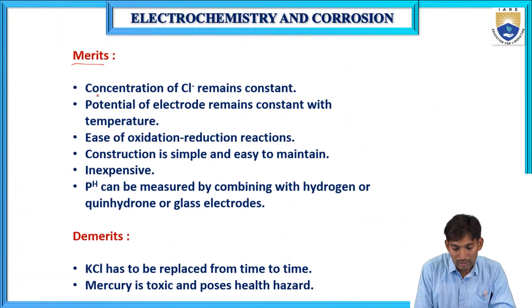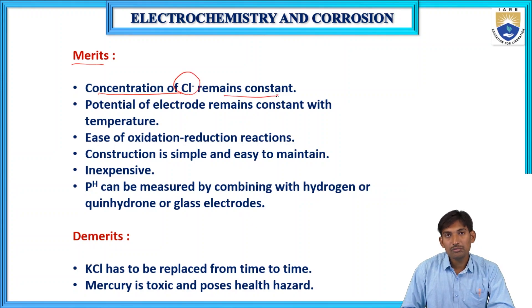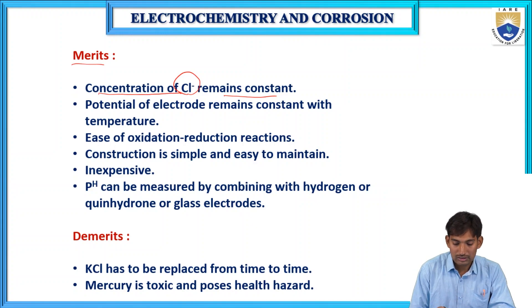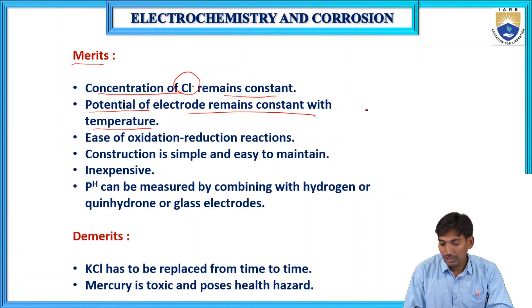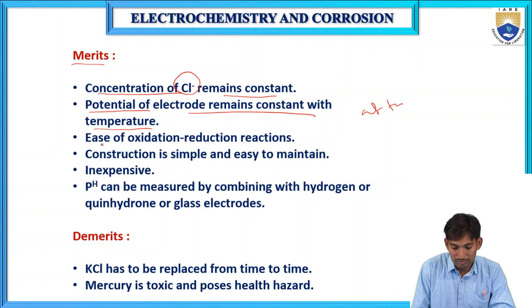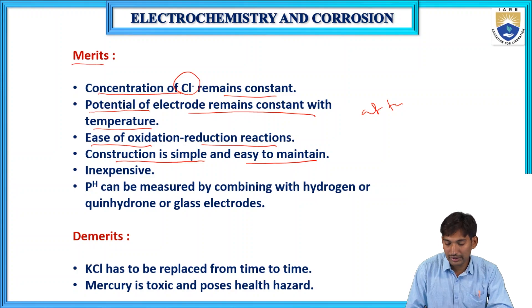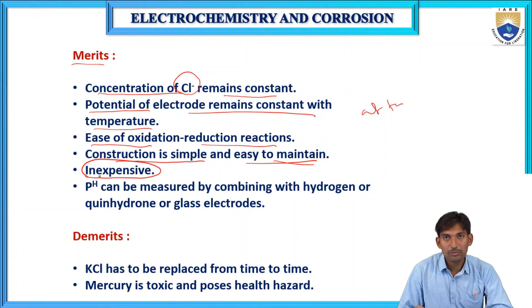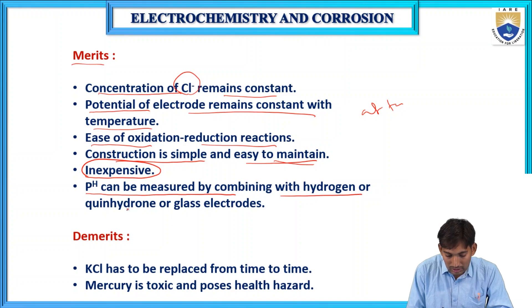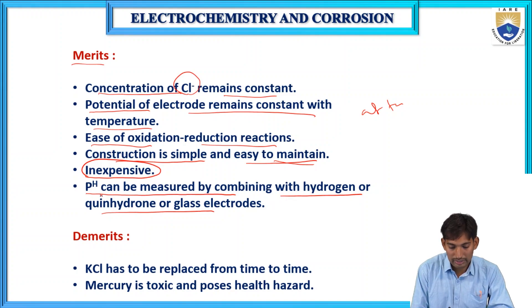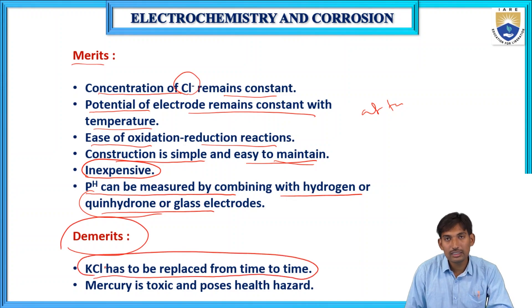Merits of calomel electrode: the concentration of Cl⁻ remains constant; the potential remains constant with temperature; oxidation and reduction reactions occur easily; construction is simple and easy to maintain; it is inexpensive; and pH can be measured by combining it with hydrogen and quinhydrone glass electrodes. Demerits: KCl has to be replaced from time to time, and mercury is toxic, posing health hazards.